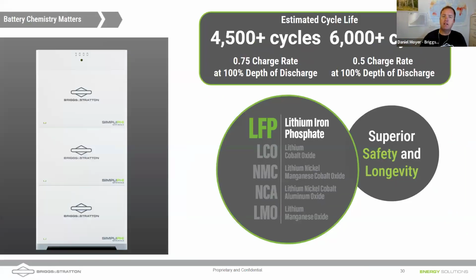LFP, lithium iron phosphate, is the chemistry we leverage in standby or backup power and grid interactive batteries. It's not the cobalt-based chemistries that we've seen in the industry. Lithium iron phosphate has a better cycle life. It's a little less energy dense, so it's heavier, but we don't necessarily mind, right? Because our batteries are stationary. I will say this, Nathan and I got a chance to check out some of Briggs & Stratton's other family of products, which is our Vanguard batteries, which are used in riding lawnmowers. Those are all cobalt-based chemistries, which is totally acceptable because we're looking for more energy density. We're looking for a faster discharge, but we're not scaling them up as big. Cycle life is important.